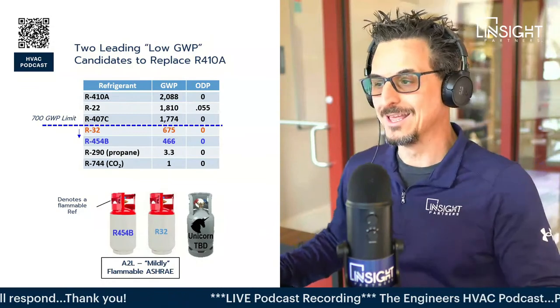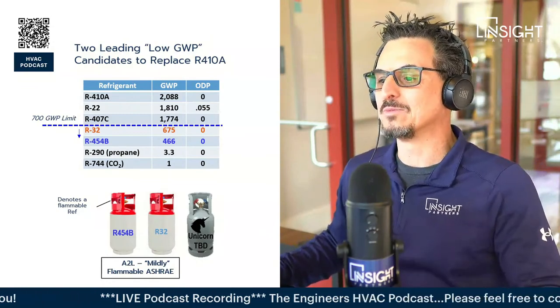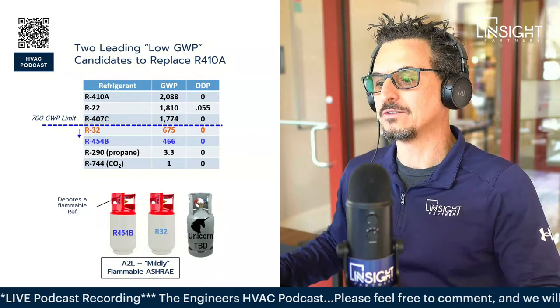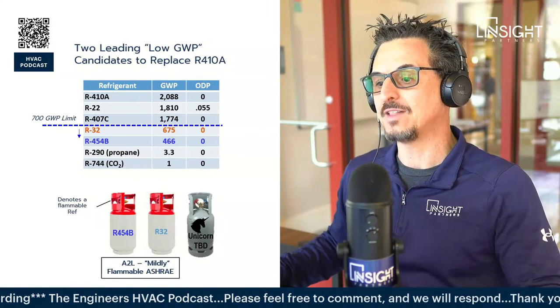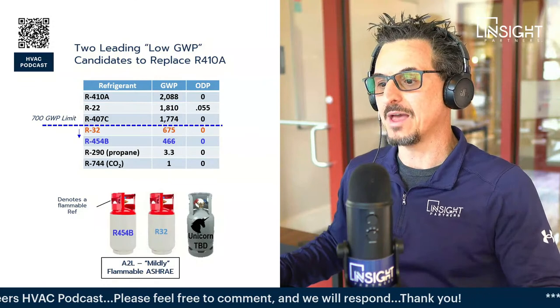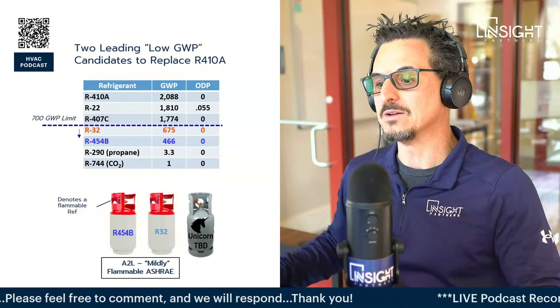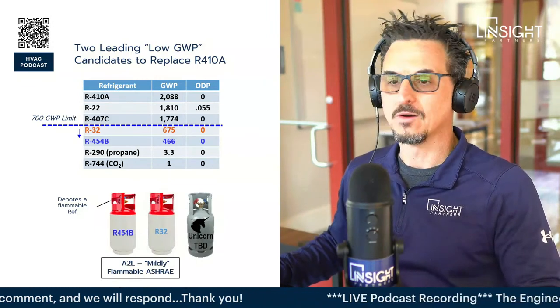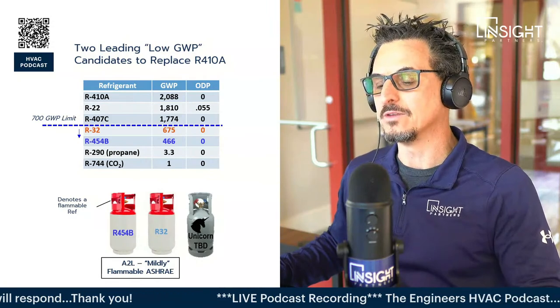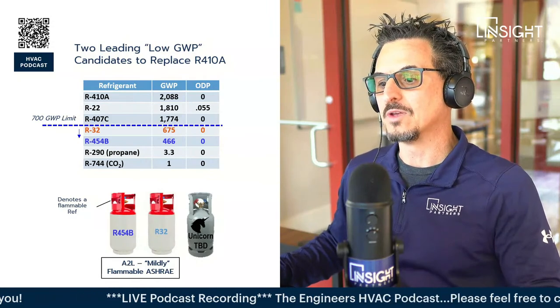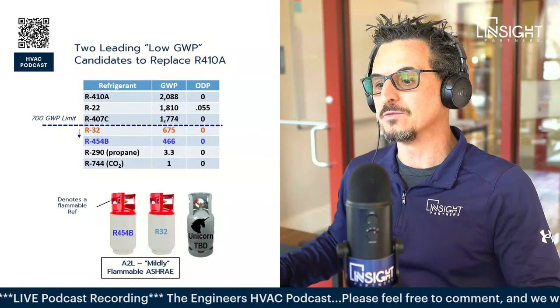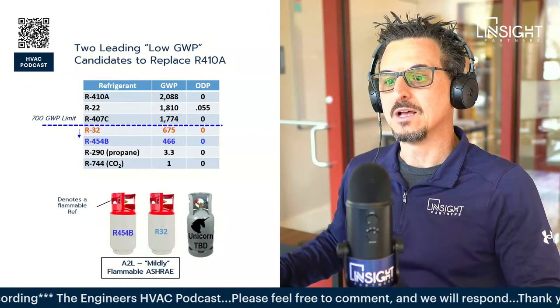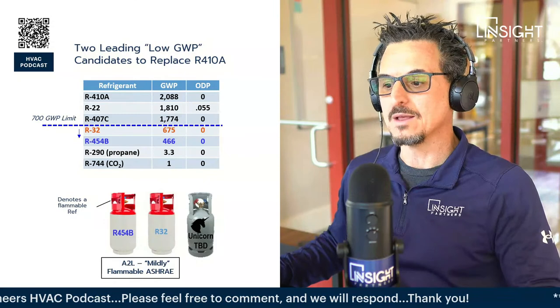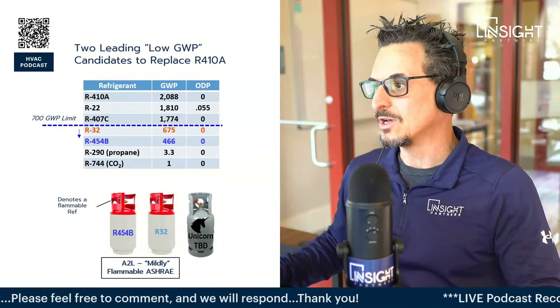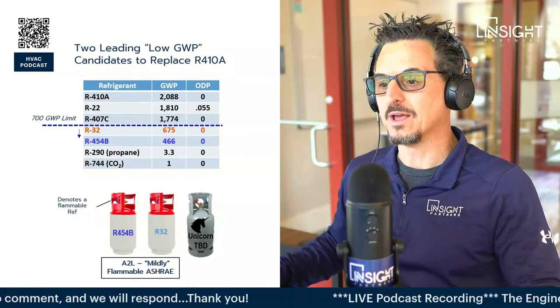This was a note to me that I'm reading out loud. No drop-in replacement for 410A, as the new candidates are classified by ASHRAE as mildly flammable. We're going to talk about that because that's a big deal, or at least the biggest deal as far as going to these refrigerants - we haven't done that before. Going lower than 700 GWP could force the industry into hydrocarbons. A common hydrocarbon is propane, and I think that would be a huge undertaking to do. I'm not sure we'd ever get there.